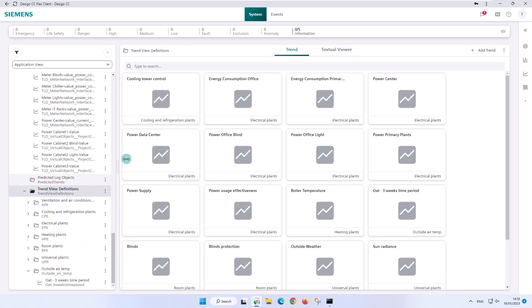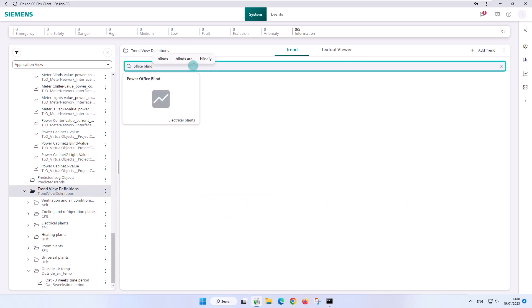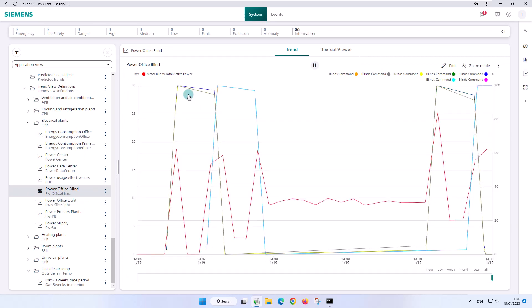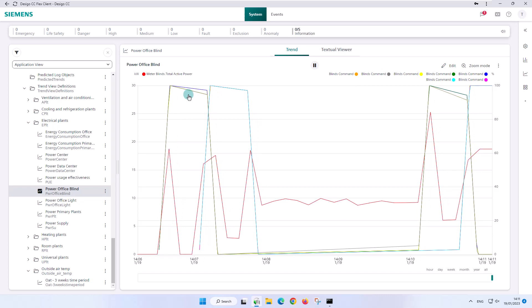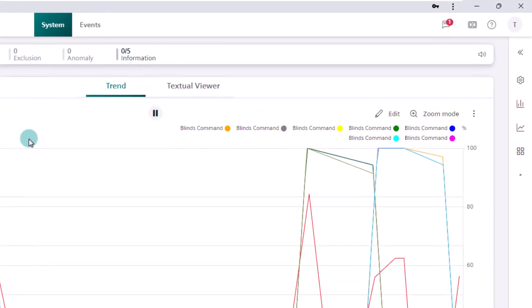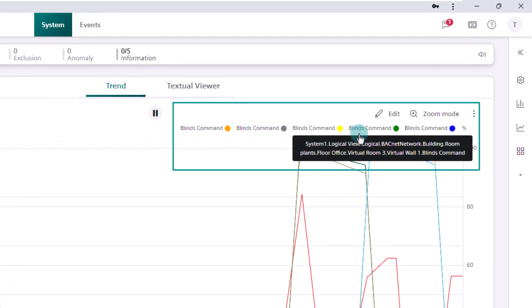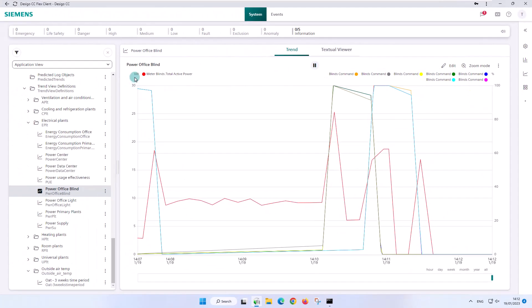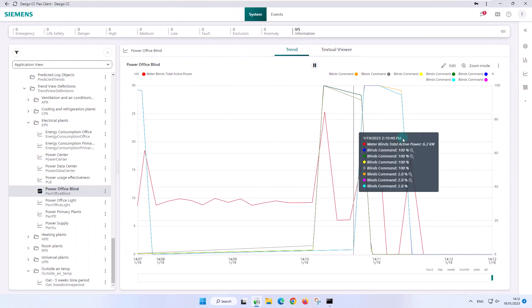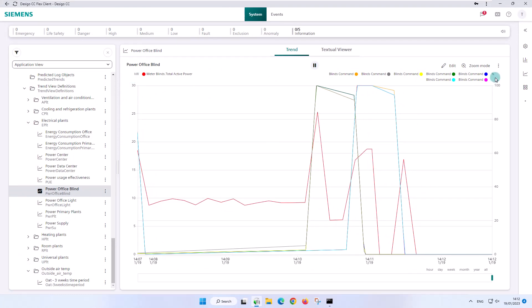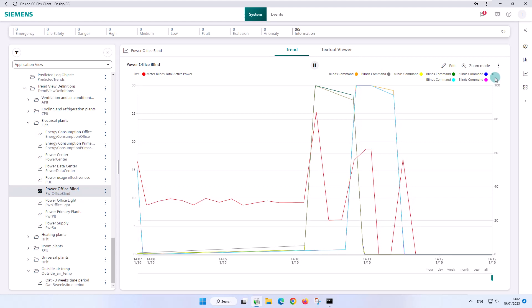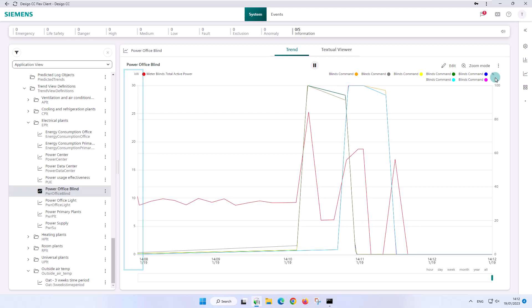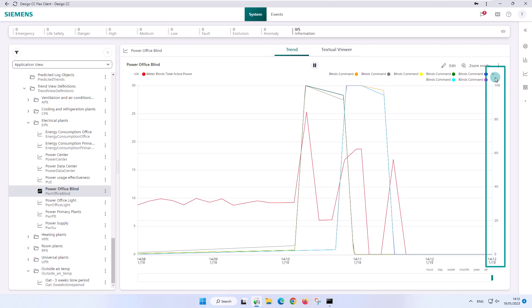We change the trend object type and open a trend view definition — more precisely, the power office blind — to see the difference between a single data value record and a record with multiple data objects. The legend and the diagram show us the records of a total of eight data values, including colors assigned to the data objects. In terms of the unit, one differs from the other seven. Consequently, two y-axes are provided in the chart. On the left y-axis we have the current power in kilowatt unit, and on the right y-axis the blind commands in the percentage unit.